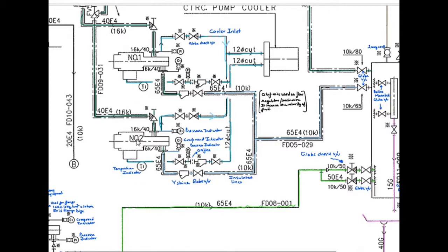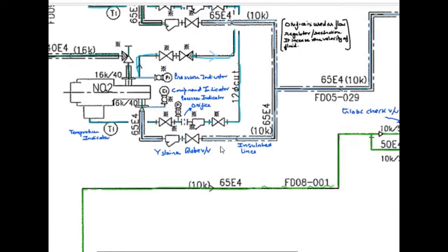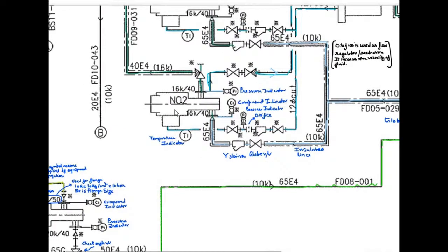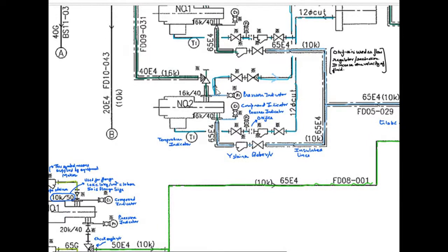In the suction line, you can see, we have a globe valve, we have a Y strainer. And on the suction side, we have a compound indicator. And on the discharge side, we have a pressure indicator. Now, we have a cooler to cool these circulating pumps.